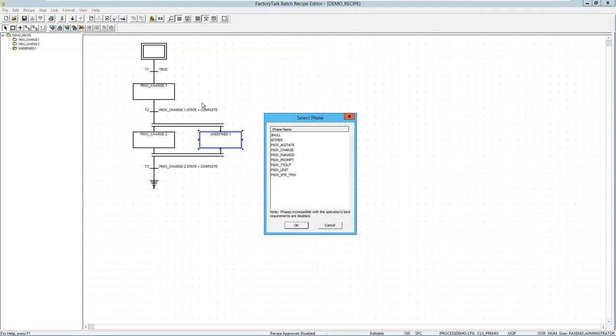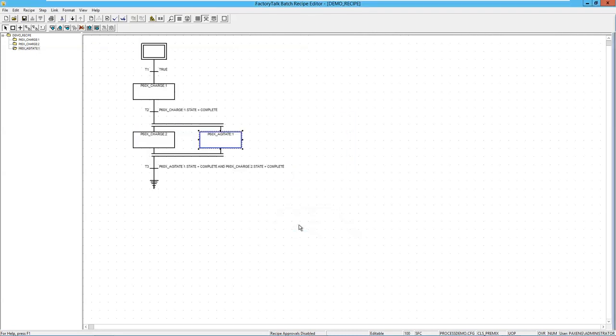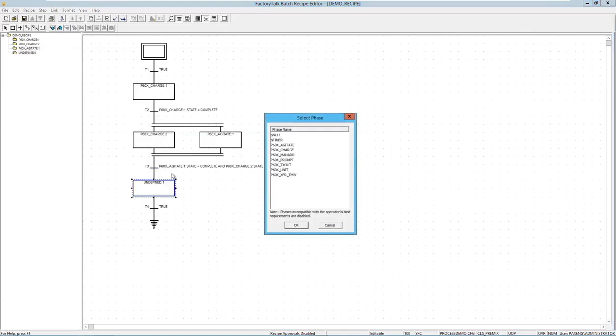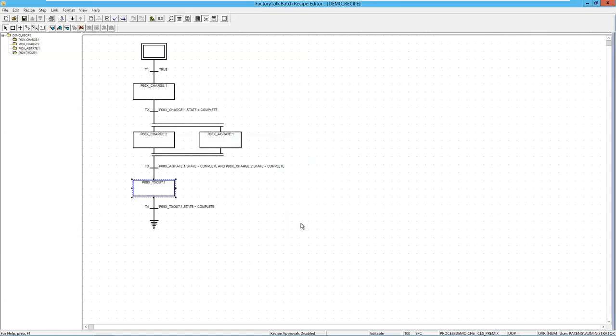I'm going to add a step. The recipe editor then asks which equipment phases we'd like to run, and this list is filtered so I can only select things that I can run on my pre-mixer. Let's select the charge equipment phase — I'm going to charge material into my pre-mixer. Then we'll do another charge, and also in parallel do some mixing — I'll run the agitator at the same time. Then once I've made my material, let's add another step to transfer it out into final product storage.